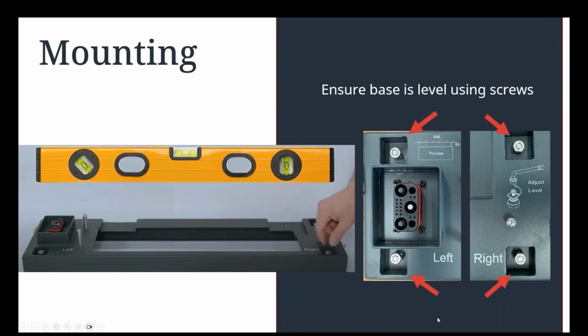Ensure that the base is level. So we have these 4 base level screws, which you can adjust, that the system is level, and it also says on top, I hope you can see my mouse here, the base and the distance towards the wall, which gives you a very good indication on where things need to go. It's a modular concept, no wires are required, so you just pretty much stack the modules on top of each other.